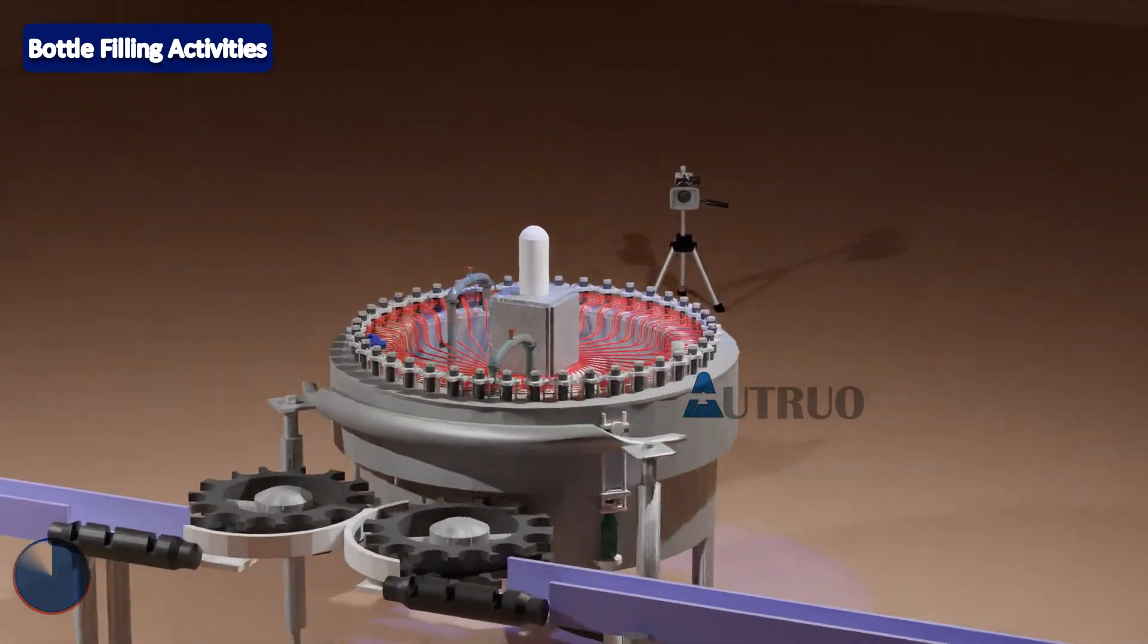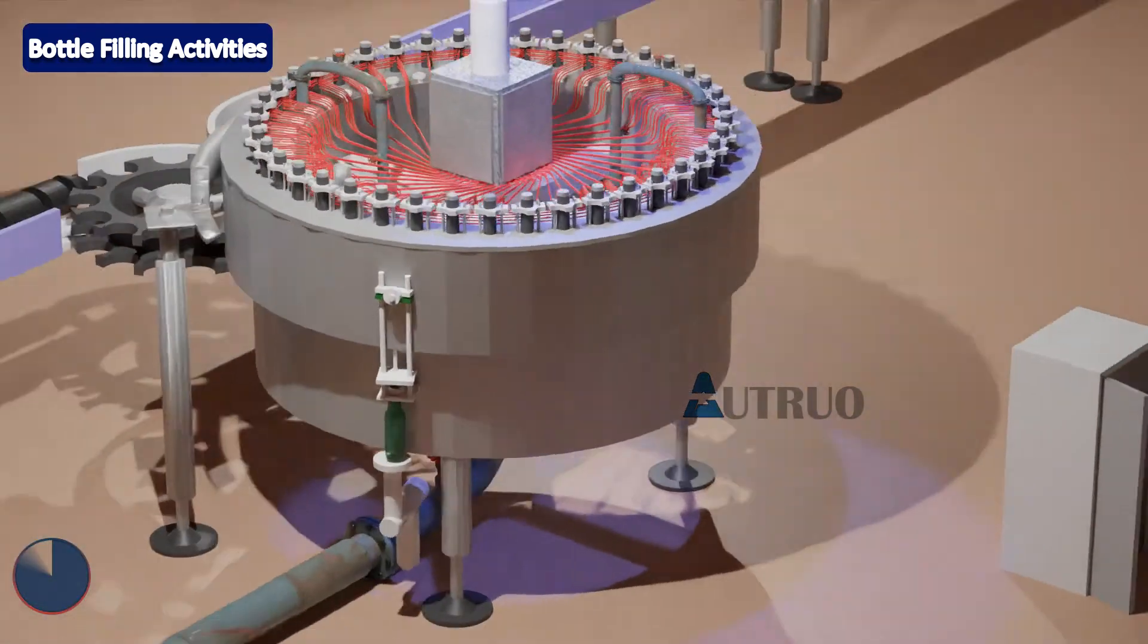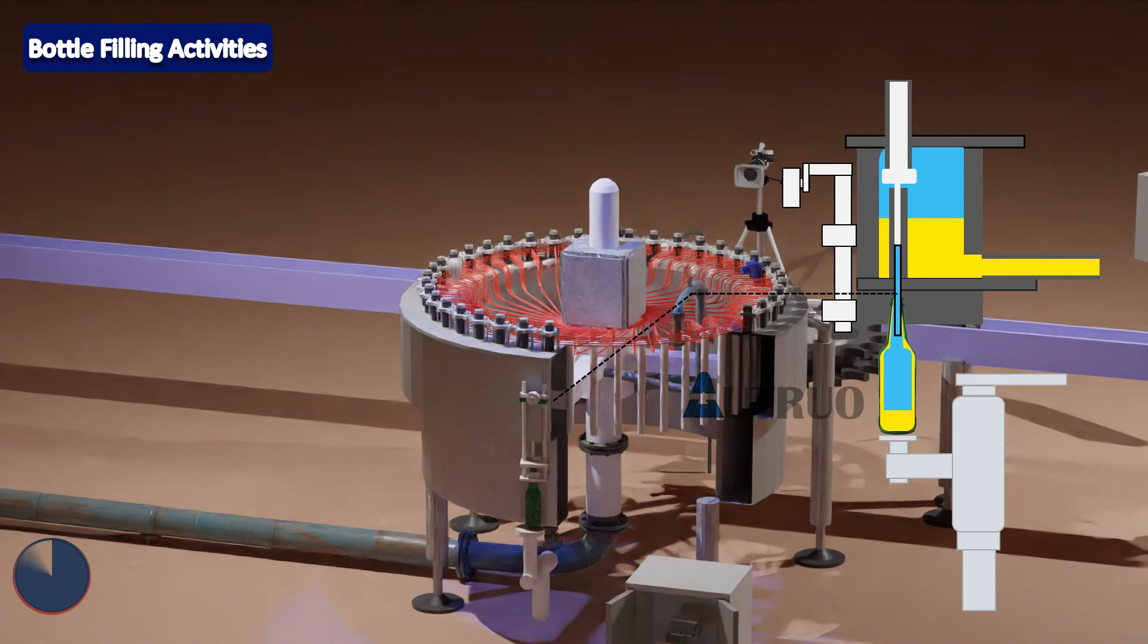Now when the filler rotates from 25 degrees to 65 degrees, the PLC will use compressed air to activate the filling valve, and the bottle will be filled with product. As the bottle fills up, it will fill to the extent that the vent tube starts taking some product in. This will trigger the filler to stop filling and as such filling will stop.